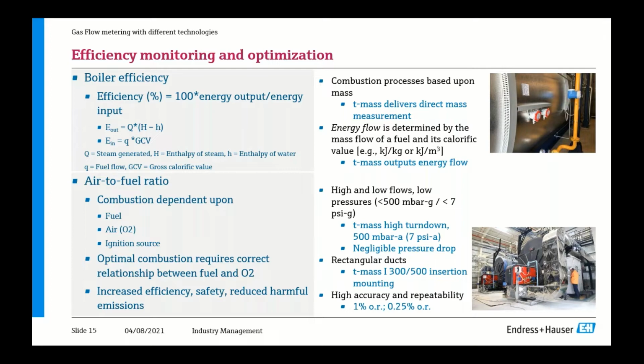In this regard, T-mass, thermal mass, is also ideally suited for that purpose. Very often, because of changing operating points of the boiler, there may be needs for low to very high flows. The T-mass device has a very high turn down, typically 100 to 1. It can also be used very well in low flows where there are also low pressures, and it causes a very small to negligible pressure drop due to its design.